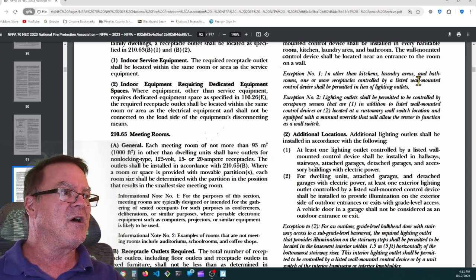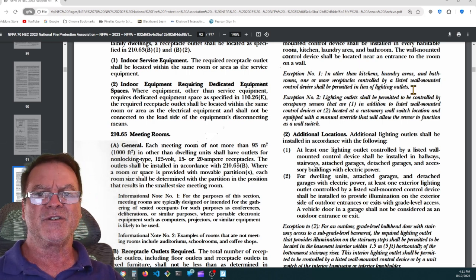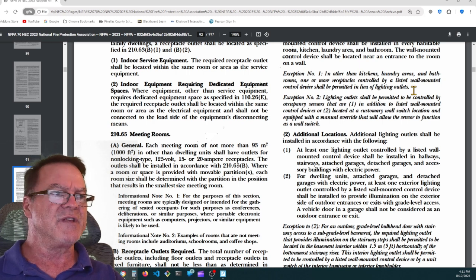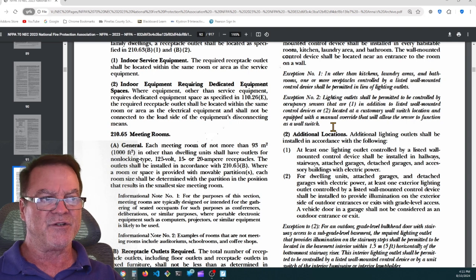In other than kitchens, laundry areas, and bathrooms, one or more receptacles controlled by a listed wall-mounted control device shall be permitted in lieu of lighting outlets. So that's giving the contractor permission to just half switch a receptacle and use that as the lighting outlet. It's a lot less expensive. Exception number 2, lighting outlets shall be permitted to be controlled by occupancy sensors that are 1, in addition to listed wall-mounted control devices, or 2, located at a customary wall switch location and equipped with a manual override that will allow the sensor to function as a wall switch.